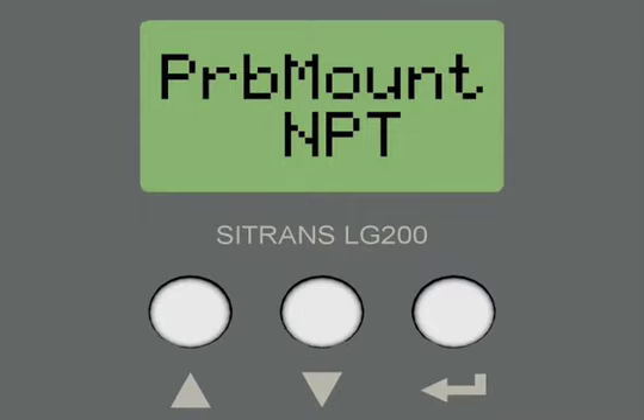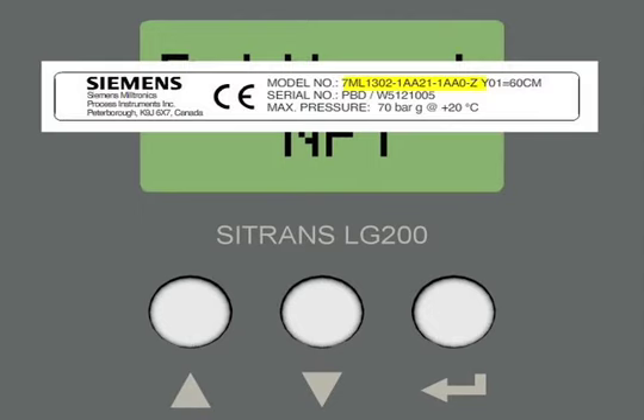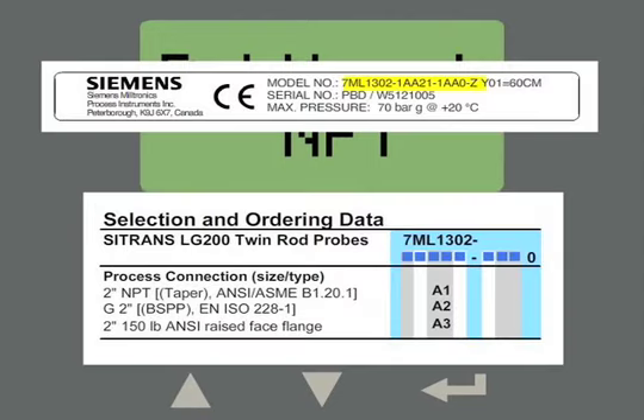The next parameter is the probe mount. There are 3 choices in the probe mount parameter: NPT, BSP, and flanged. Using the probe part number and the LG200 catalog sheet, we can verify which mounting thread we have. It is important to do this because the measurement reference point for the threaded connections are different between the NPT and BSP types. According to the product configuration on the catalog sheet, the 10th and 11th digits of the part number represent the process connection. A value of A2 confirms that the probe we are using has a BSP thread.